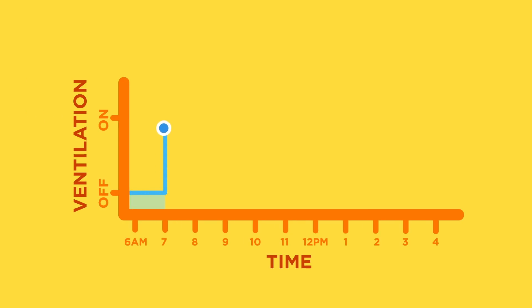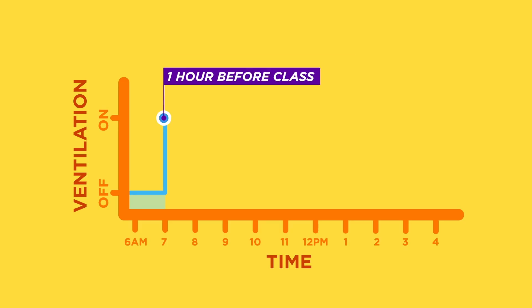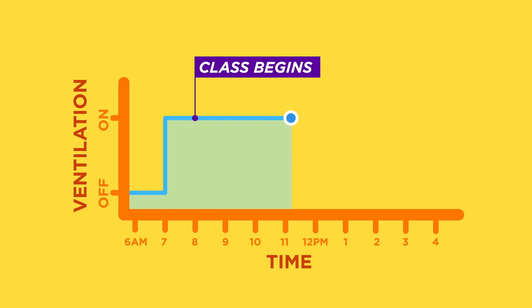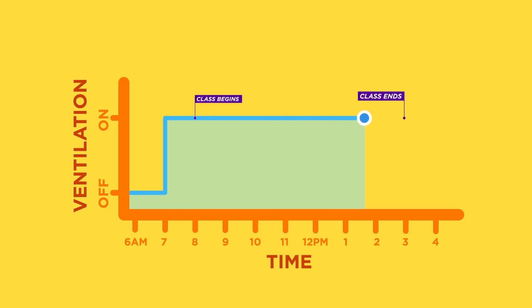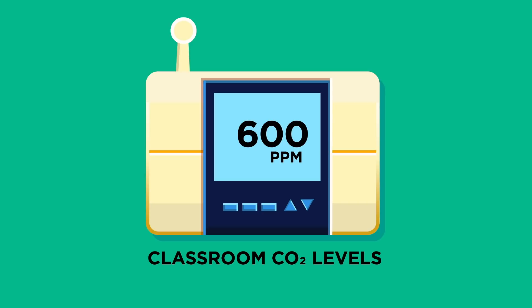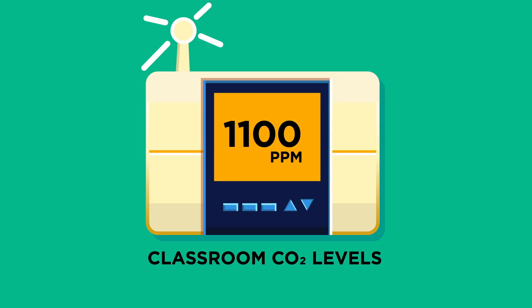The fan supplying the ventilation to the classroom must run at least one hour before scheduled occupancy and during all occupied hours. In addition to testing and adjusting ventilation rates periodically, continuous monitoring of classroom CO2 levels is recommended to quickly detect ventilation problems.